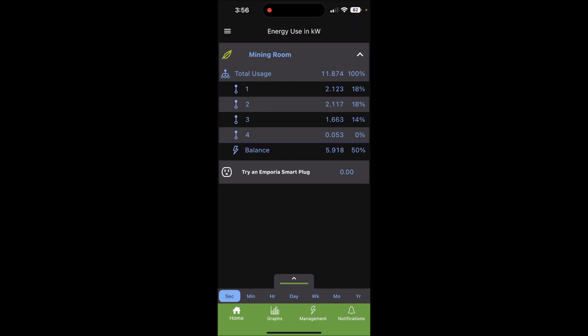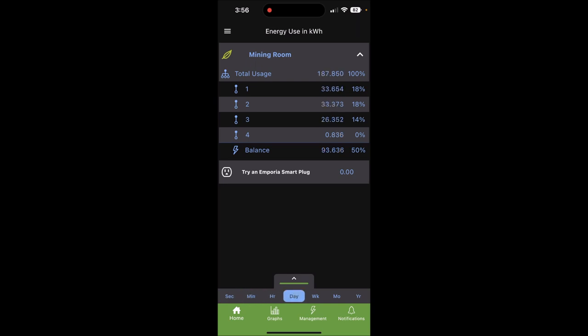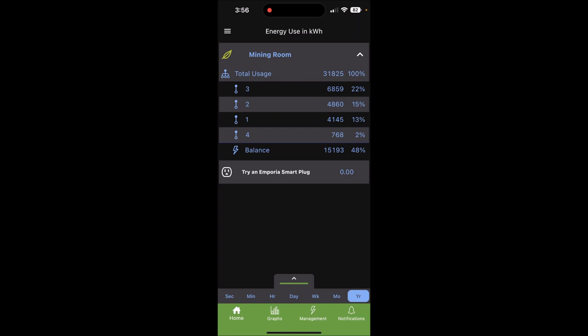Right now that panel is drawing 11.87 kilowatts, and it gives you a breakdown of each of the lugs, which is basically just pretty much doubled. So that's about 4200, then 4200, 3200, and then this is like the 20 amp outlet which is barely drawing any.